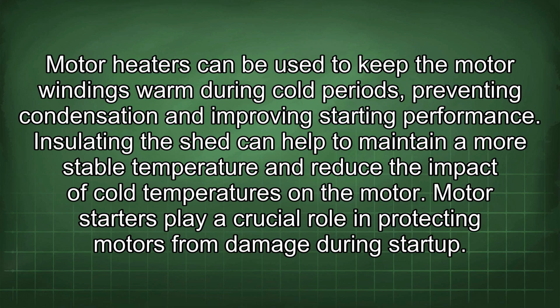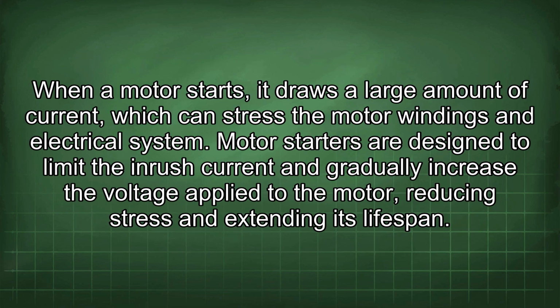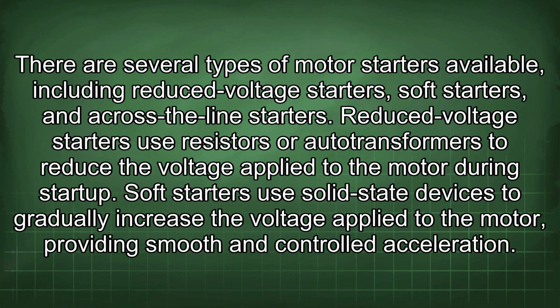Motor starters play a crucial role in protecting motors from damage during startup. When a motor starts, it draws a large amount of current, which can stress the motor windings and electrical system. Motor starters are designed to limit the inrush current and gradually increase the voltage applied to the motor, reducing stress and extending its lifespan.